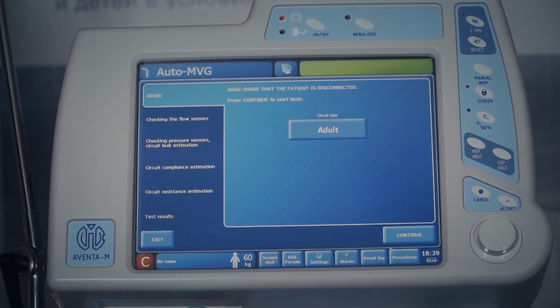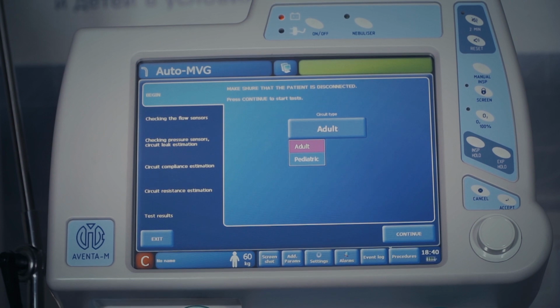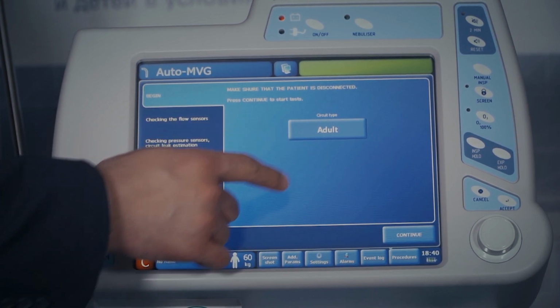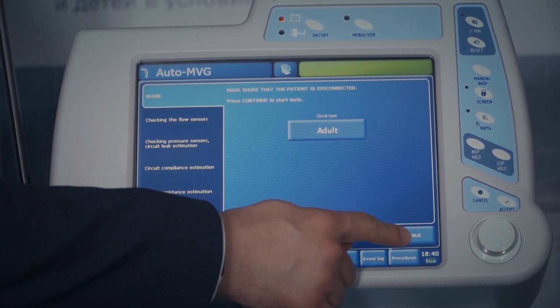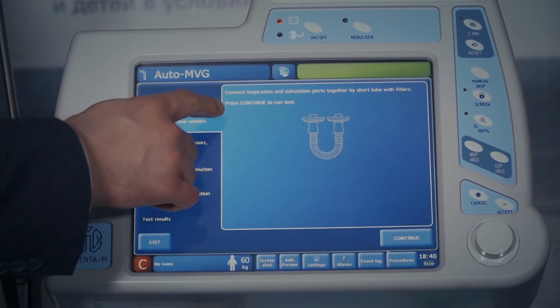Prior to ventilating a patient, certain tests and calibration operations shall be performed. These tests shall be performed after each replacement of a breathing circuit, flow sensor, or bacterial and viral filters. Press Tests key on the standby screen. Make sure the patient is disconnected from breathing circuit. Select the type of breathing circuit used, adult or pediatric. To start the tests, press button Continue.